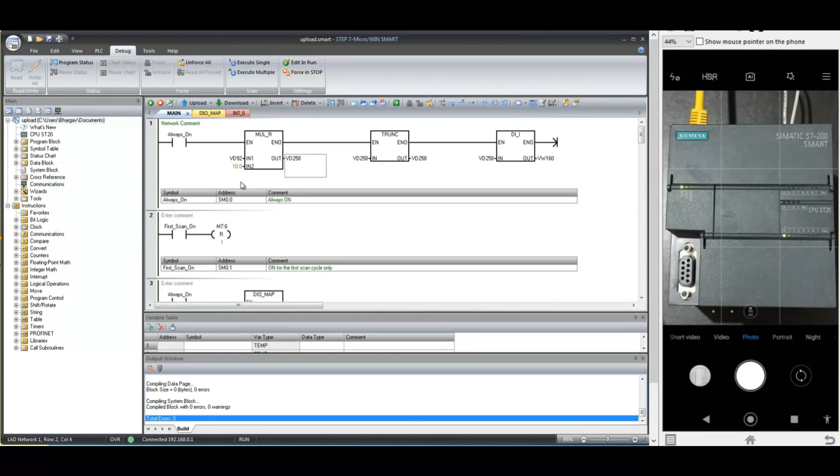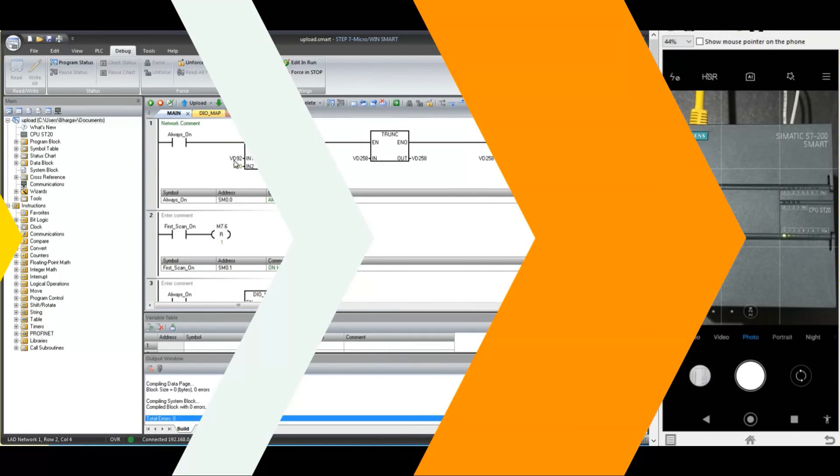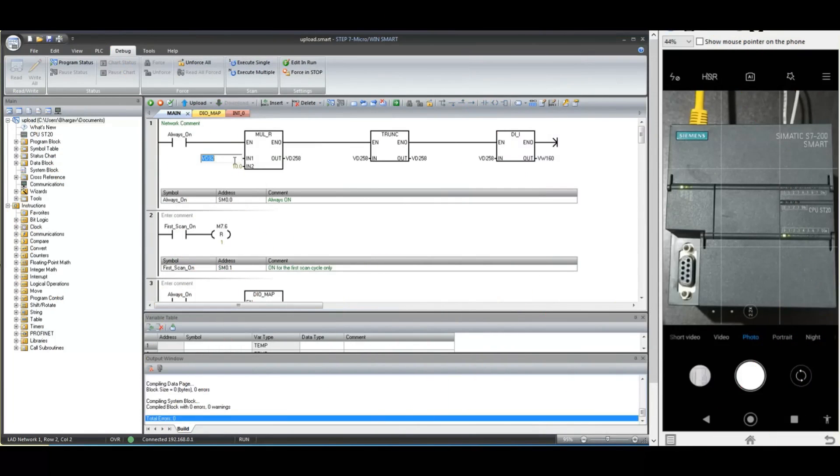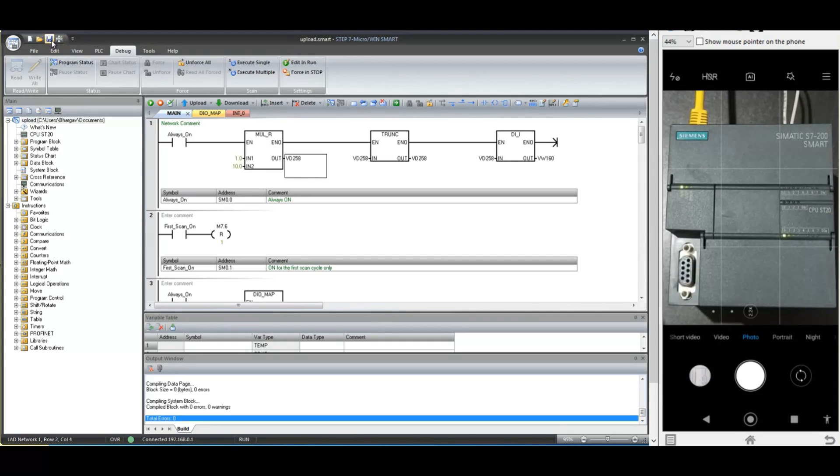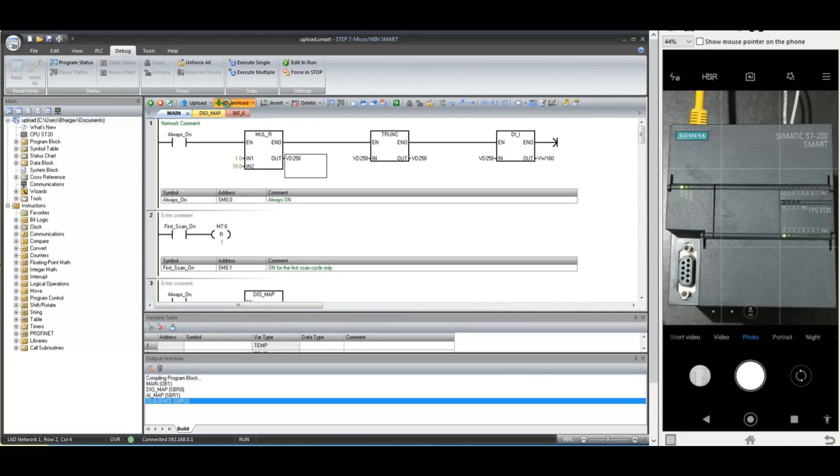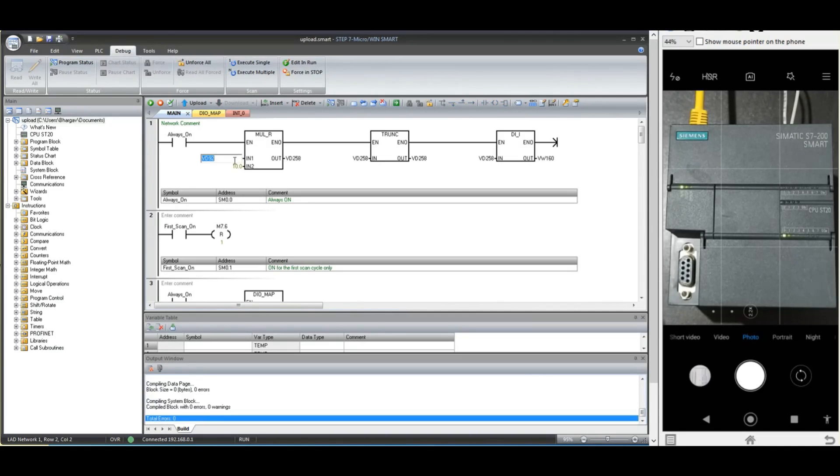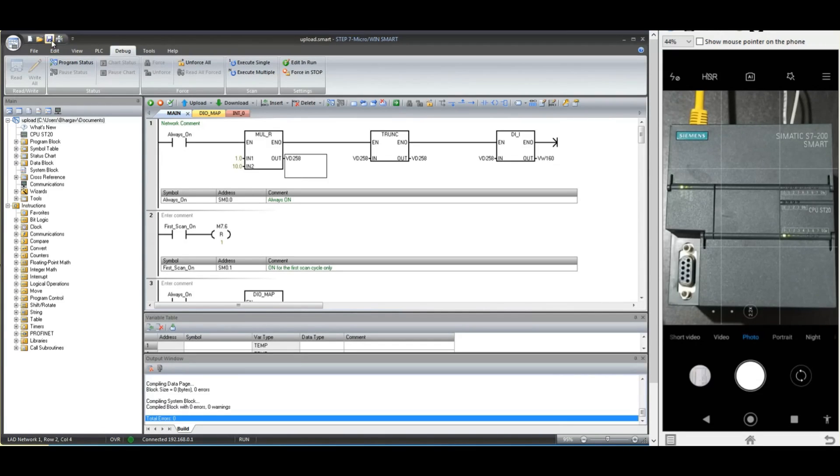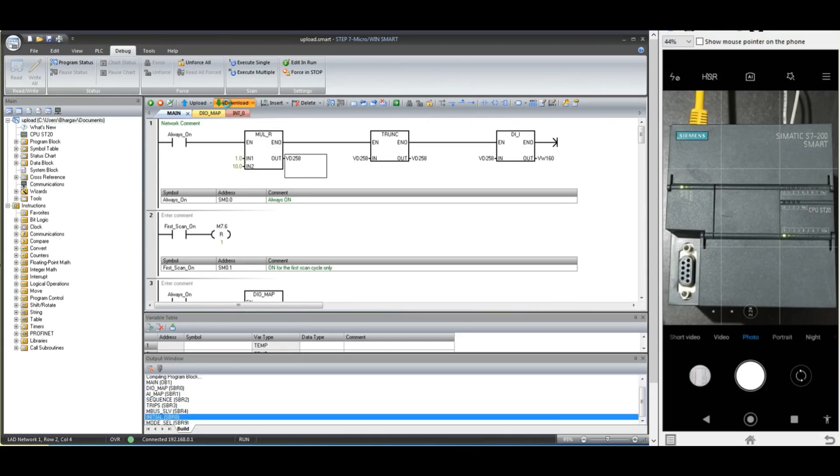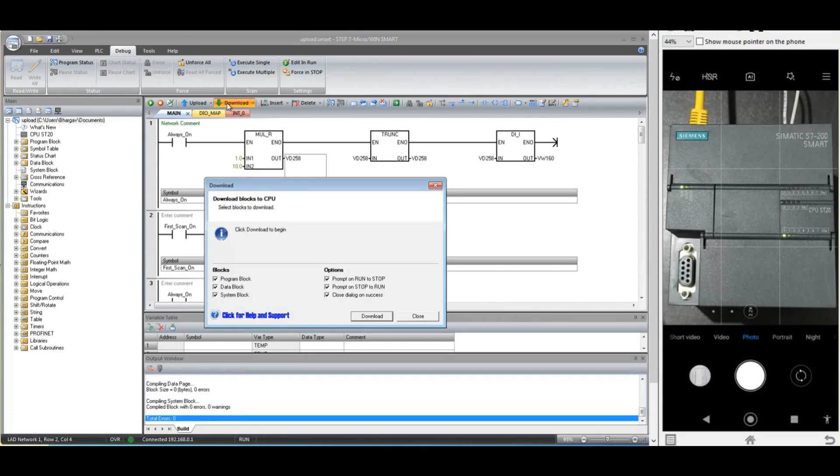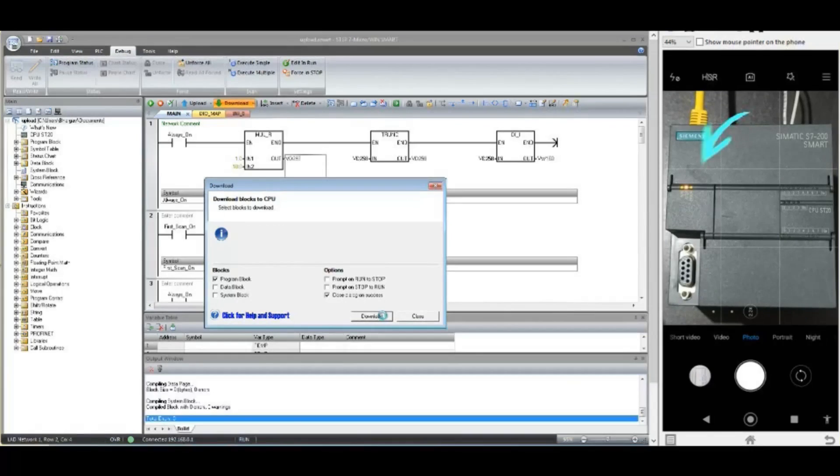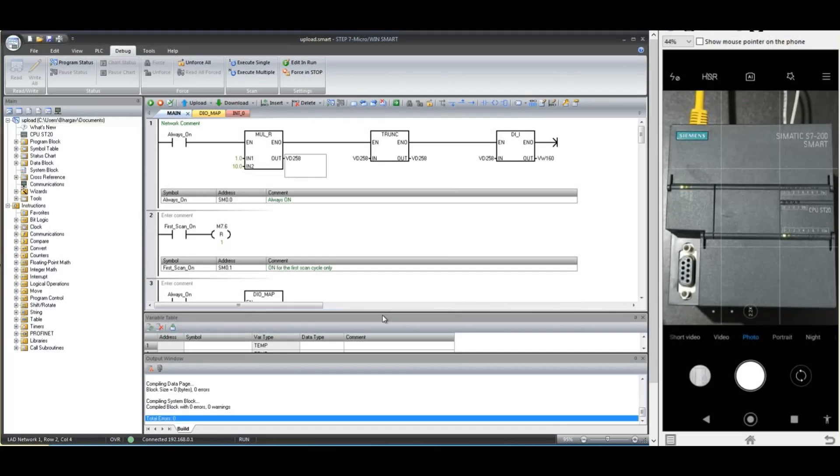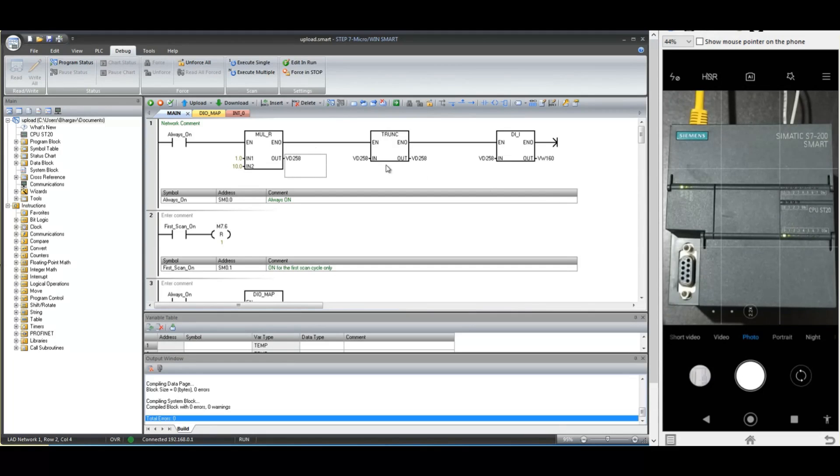Now let us try downloading only program without edit in run mode. But this time I am selecting the same options those were selected during the download in run mode. Closely observe this run and stop LED on the CPU. PLC is going in stop mode for a very few seconds and then again going back to run mode. That means to download the program without stopping the CPU, you must use the edit in run mode option.